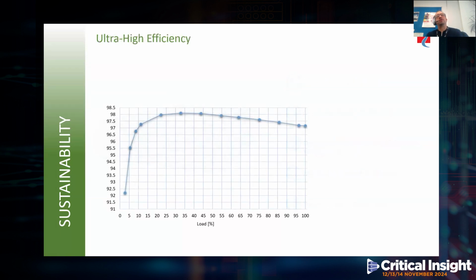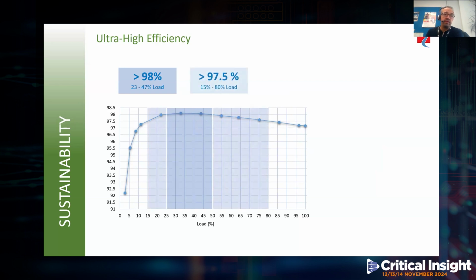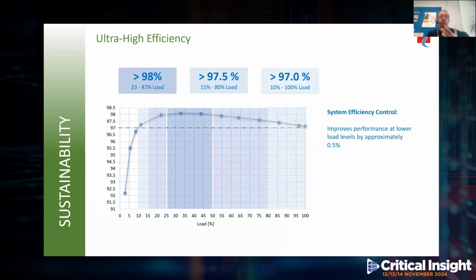If we take a closer look at the actual efficiency curve, we can see that between the load levels of 23 to 47%, the system operates at an efficiency greater than 98%. Then as we widen this load level between 15 to 80%, the system still continues to operate at an efficiency greater than 97.5%. And between the load levels of 10 to 100%, the system is still maintaining an efficiency greater than 97%. Now, in addition to this, the efficiency control mode, as mentioned earlier, can help improve the overall efficiency by 0.5% at much lower load levels.